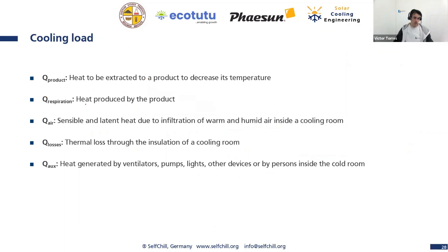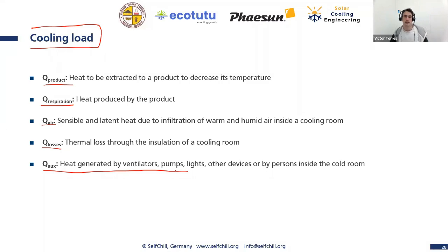As a summary, the cooling load is a sum of different factors: the Q product (energy to cool down the product), the respiration energy generated by the product, the energy to cool down the air, the energy needed to keep the cold room cold (thermal losses), and the heat generated by ventilators, pumps, and persons inside. So we have 5 factors to consider to calculate the cooling load of a storage room.